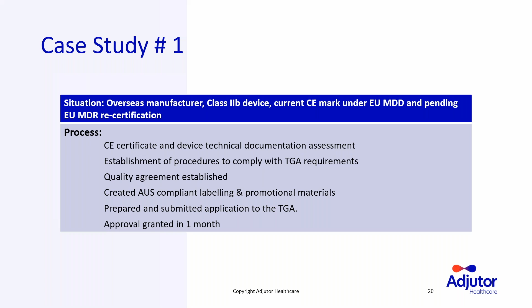First, we determined the Australian device risk category and also confirmed that their overseas CE certificate was indeed acceptable in Australia. We worked with a local Australian entity, known as the sponsor, who is responsible for the product registration. We established the necessary procedures to comply with the TGA requirements, and as part of that, we facilitated the execution of the quality agreements between the sponsor and the manufacturer. Afterwards, we created Australian-specific labeling and promotional materials and prepared and submitted the applications to the TGA. The approval was granted within a month.